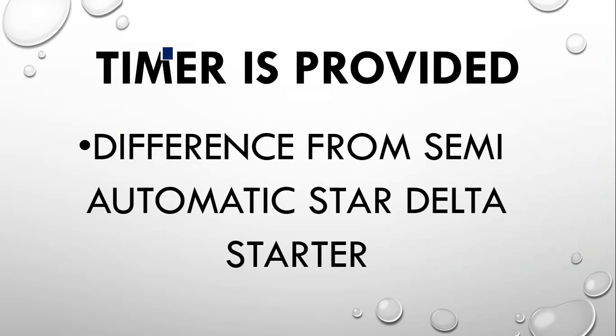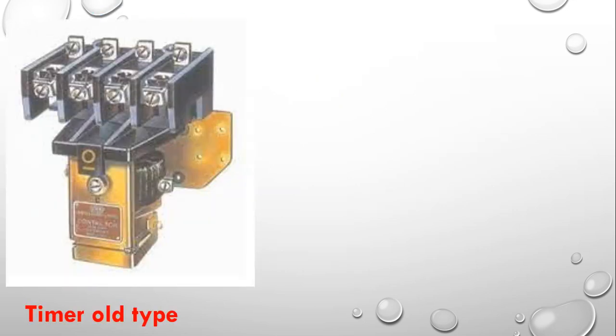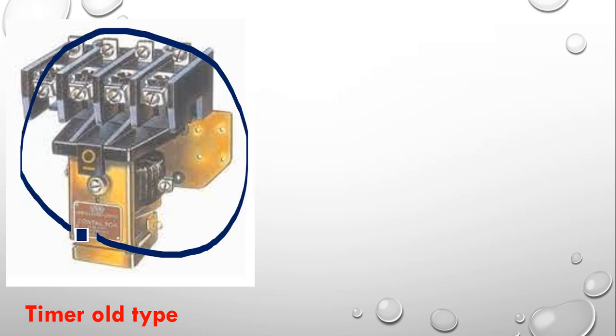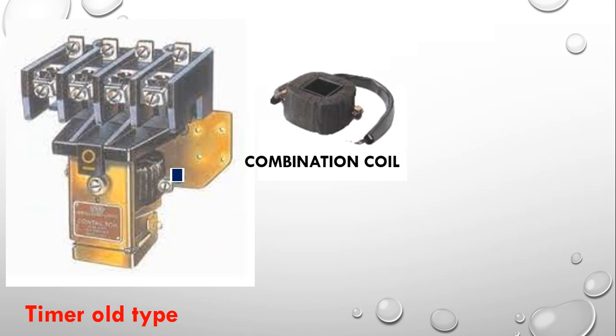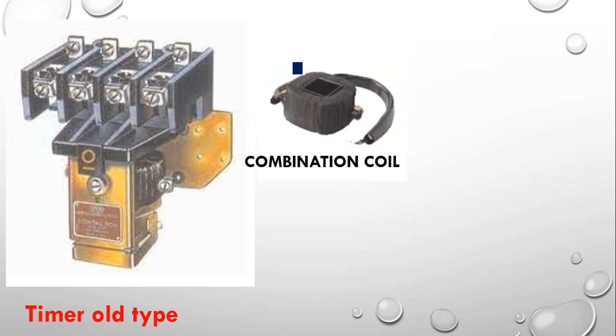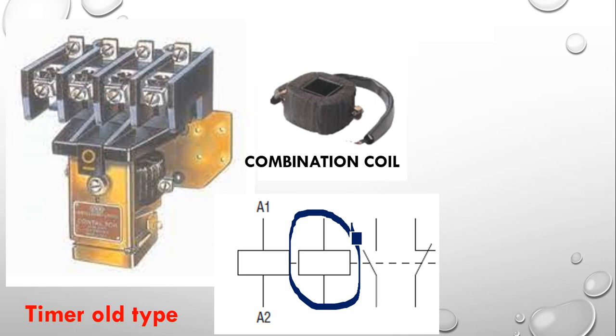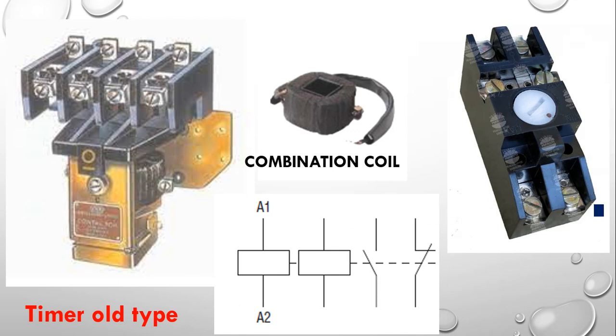The main difference between semi-automatic and automatic is the timer. There are two types: an old-type timer and a new electronic timer. In the old timer type, the no-voltage coil of the contactor is replaced with a combination coil. Inside the combination coil there is a normal no-voltage coil for standard operation, plus an additional coil. Attached to the combination coil are NC and NO contacts — this assembly forms the timer.